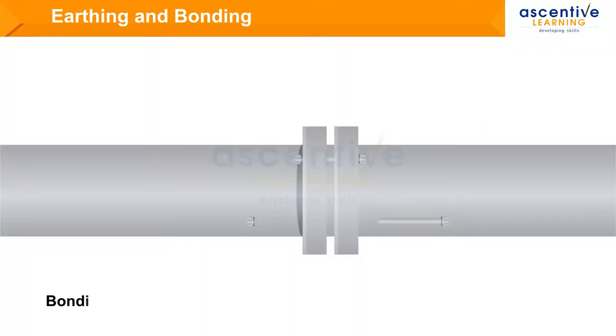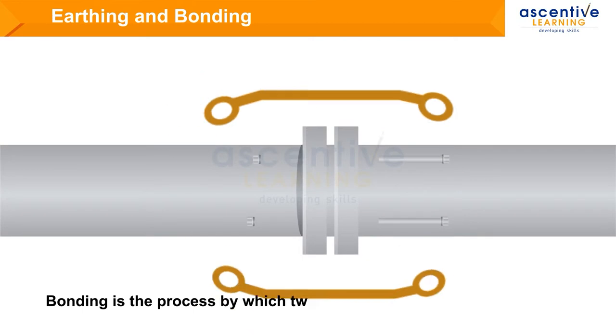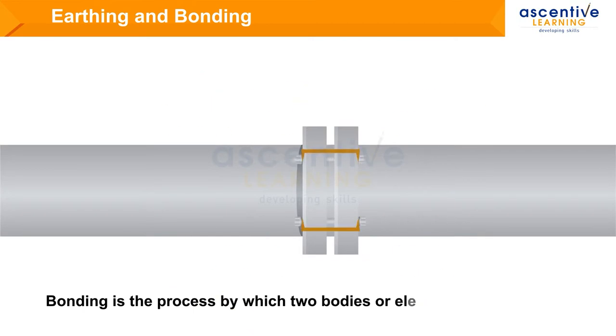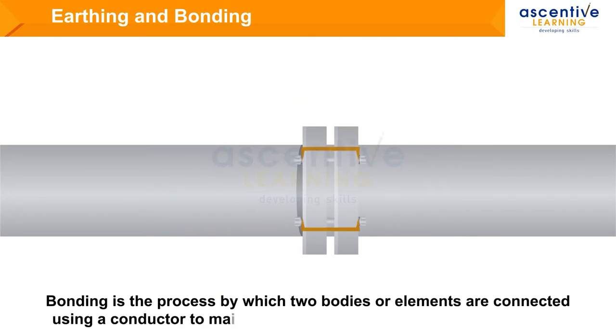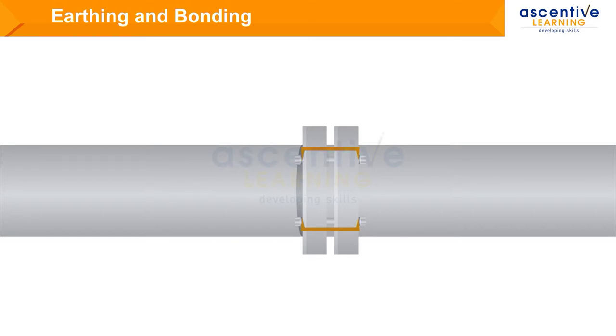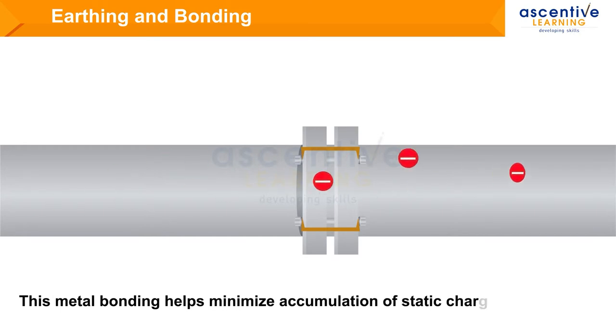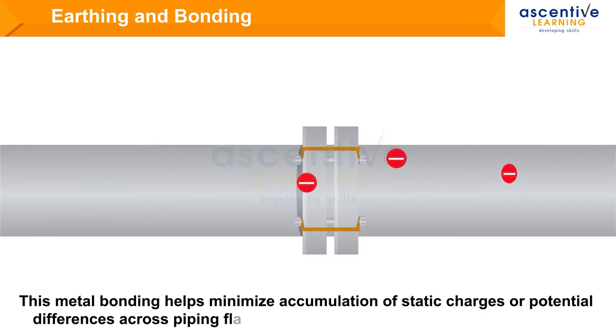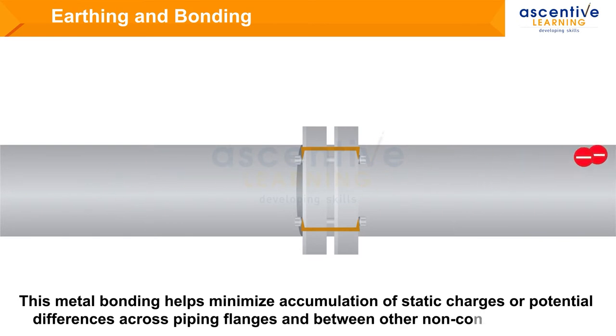Bonding is the process by which two bodies or elements are connected using a conductor to maintain electrical continuity and prevent sparking. This metal bonding helps minimize accumulation of static charges or potential differences across piping flanges and between other non-conducting joints.